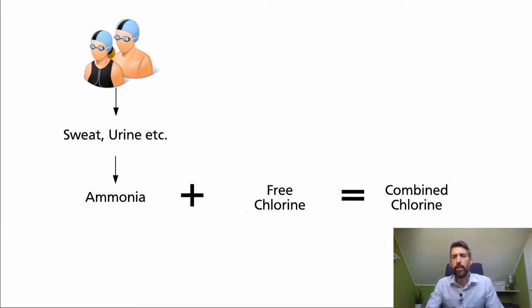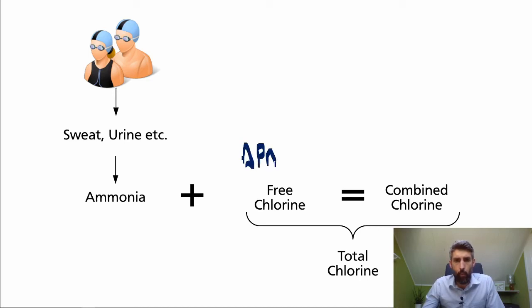There's no tablet test for combined chlorine. There's a DPD test, the DPD-1 test, that will tell you how much free chlorine you have in the pool. But in order to find out how much combined chlorine you've got in the pool, we measure something called total chlorine, which is exactly what it sounds like. It's the free chlorine plus combined chlorine equals the total chlorine. And this is measured with a DPD-3 tablet. So what you've got is the free chlorine measured with DPD-1, total chlorine measured with DPD-3.